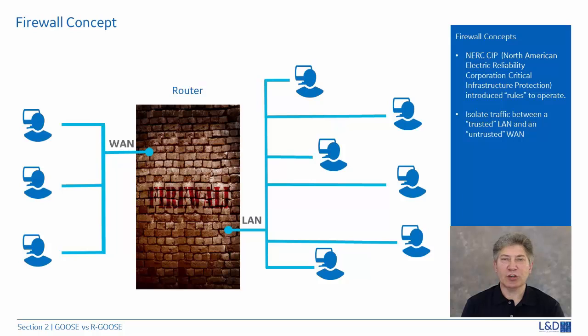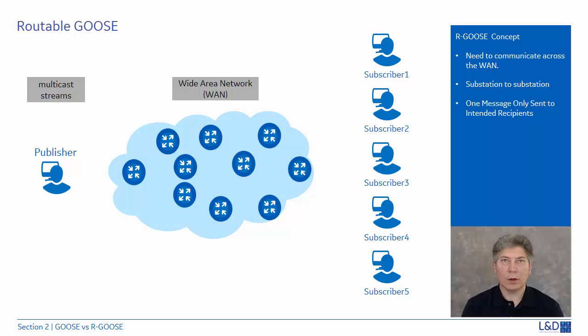As we expand GOOSE messages beyond the security of the substation, the potential for cyber attacks needed to be addressed. To avoid a rogue identity from gaining access and possibly crippling the electrical infrastructure, a group known as NERC CIP — North American Electric Reliability Corporation Critical Infrastructure Protection — coordinated efforts to improve power system security. As part of the plan, it requires the use of firewalls to block vulnerable ports and implementation of cyber attack monitoring tools. The firewall concept isolates traffic between a trusted local area network and an untrusted wide area network.